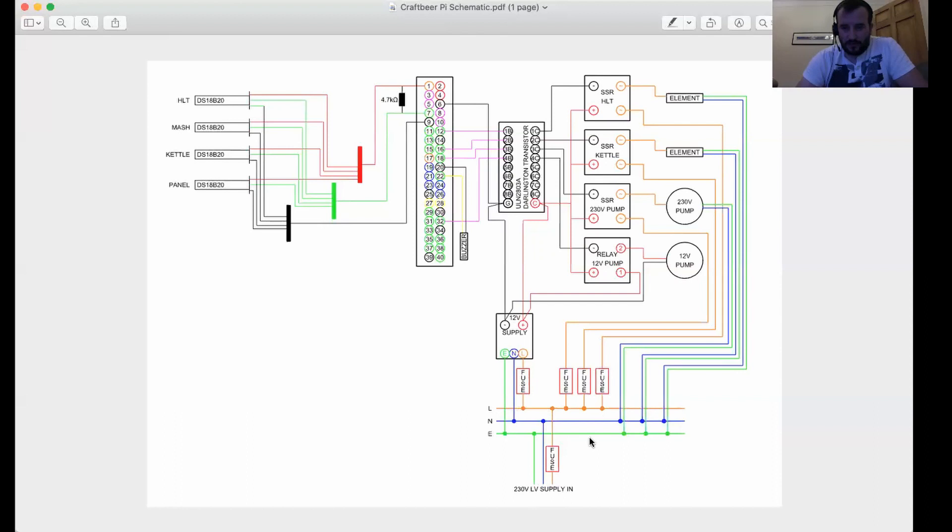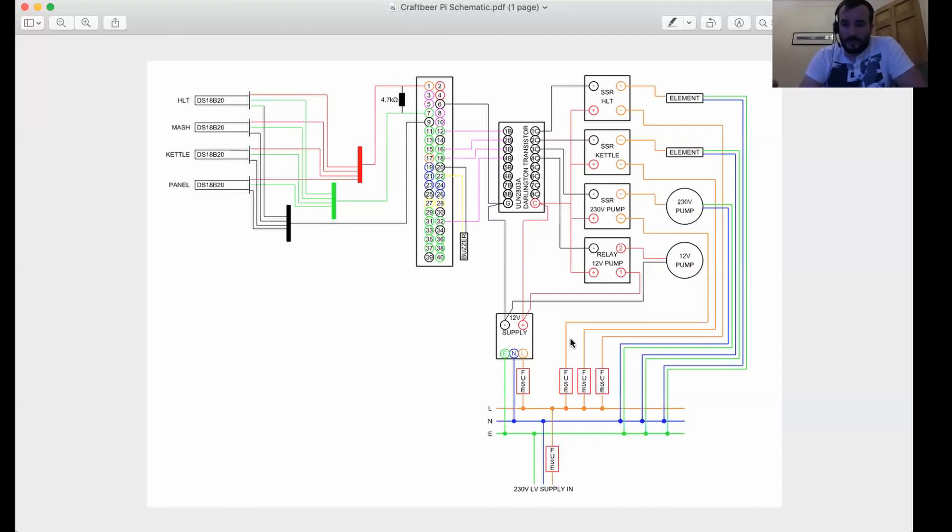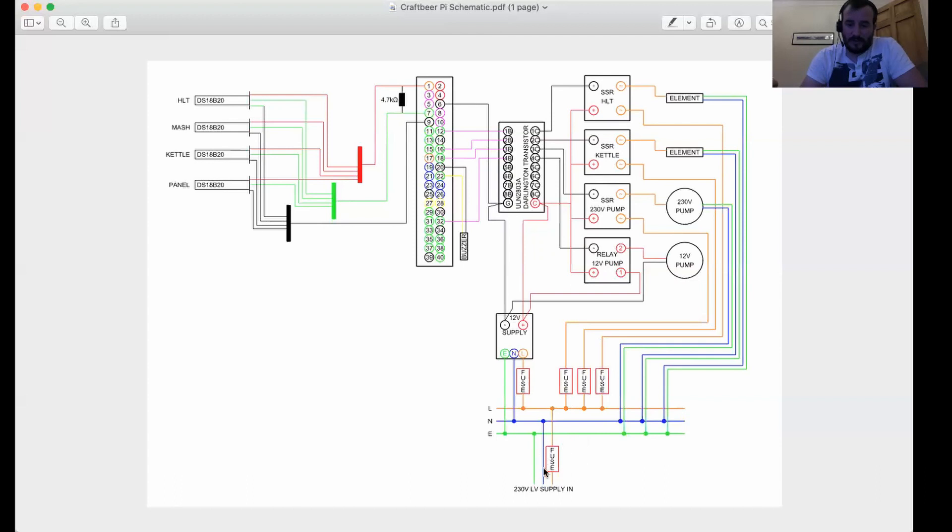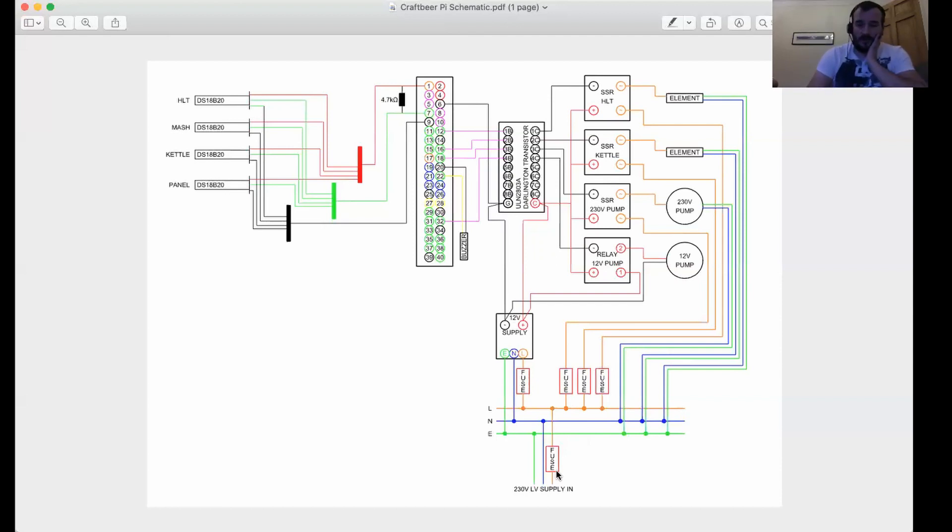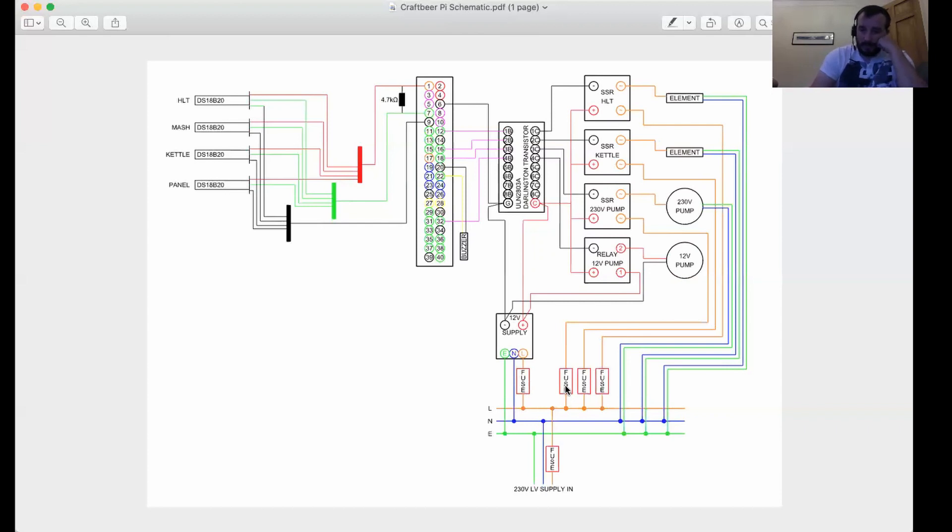That's just a bit about the LV electrical wiring. You need to ensure that your cables are wired for the current carrying capacity of the maximum current that will flow in it, which is your running current. It needs to be sized off the fuse. So effectively what I've got is a 12 volt supply here with power coming in, and then power going to my pump, power going into my kettle, and power going into my HLT.